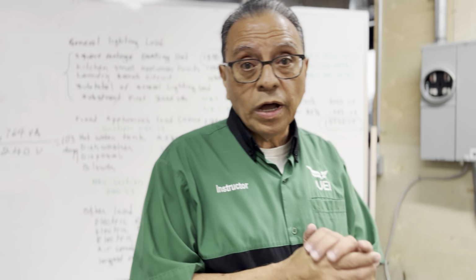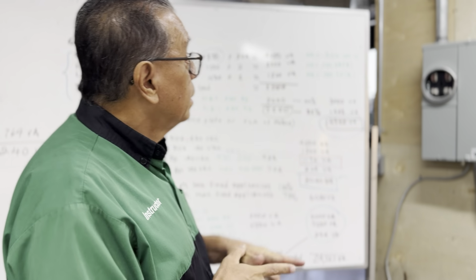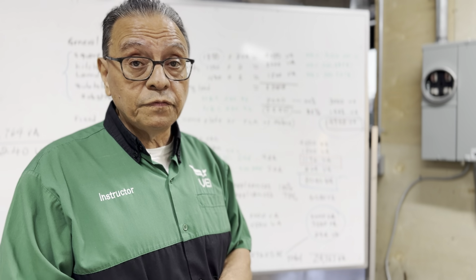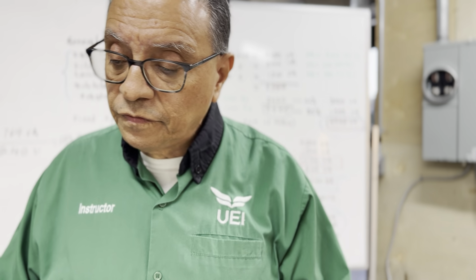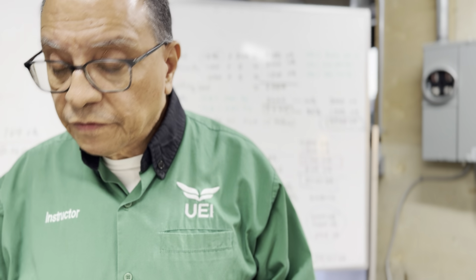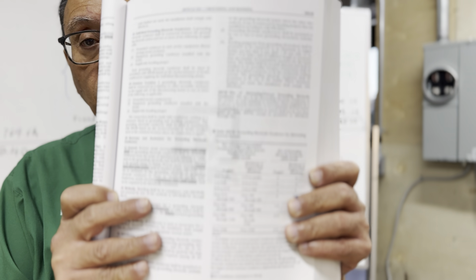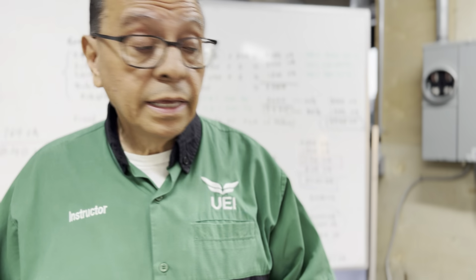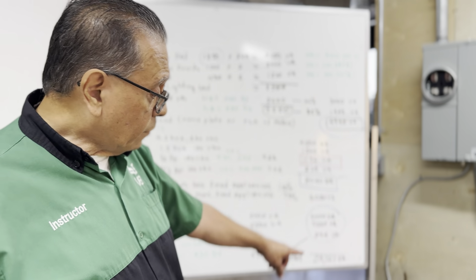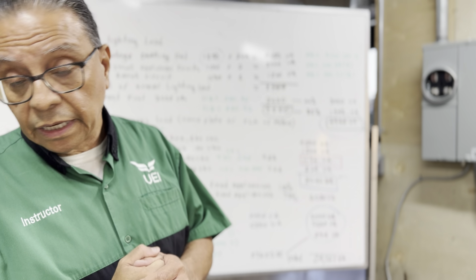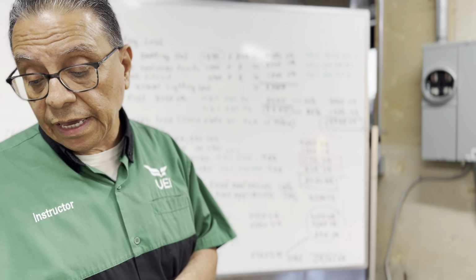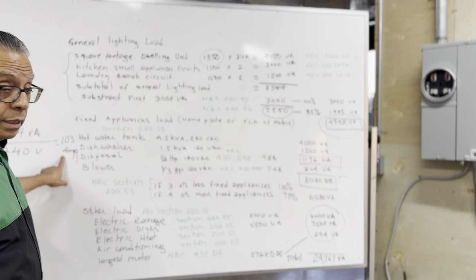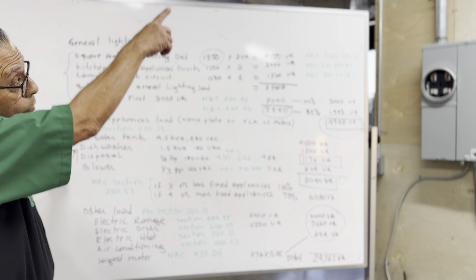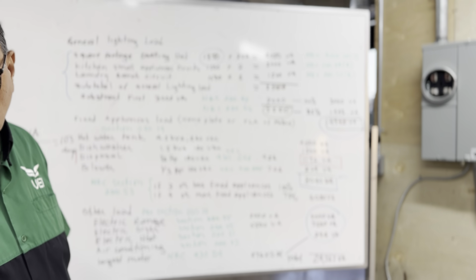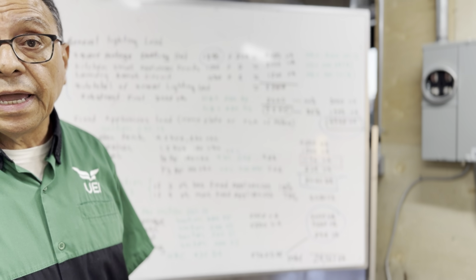So, how do I use this gauge? I need to use table 250.66 to determine the grounding electrode conductor gauge, which is number 8. If the service conductors are 2 or smaller, the grounding electrode conductor should be gauge number 8.